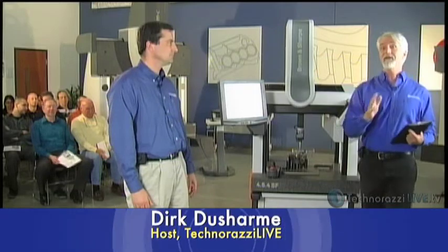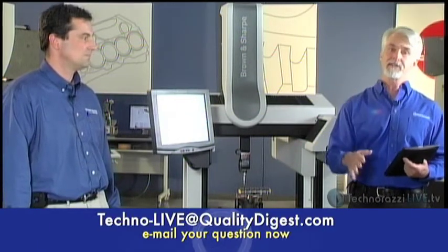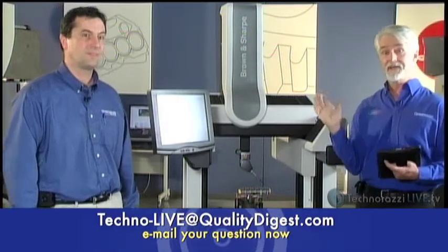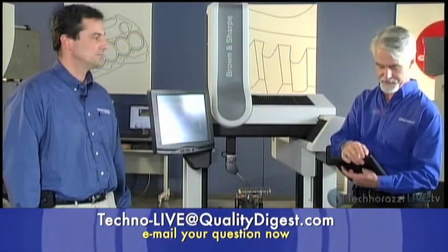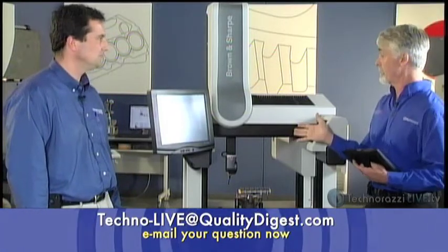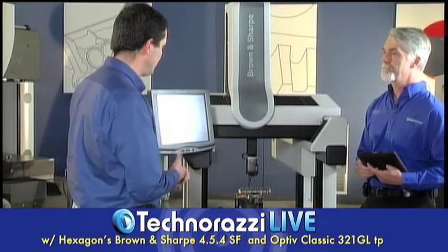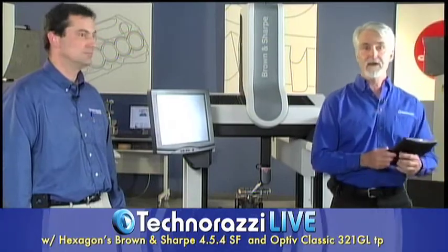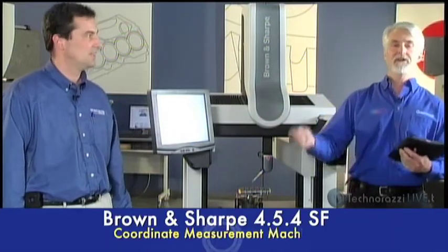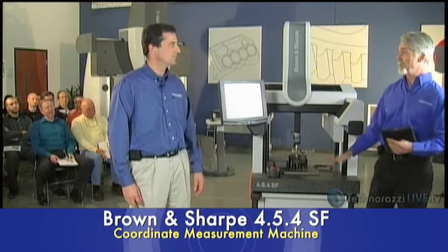Any questions, send them to techno-live at qualitydigest.com. We are going to move on to another product in a few minutes — continue to send questions even after we leave this product behind. Any kind of touch trigger probe right now and we're working on contact scanning probes. So this was the Brown and Sharpe SF shop floor CMM — shop hardened, rolls through any door, runs on 120 volts, no shop air. This is really a perfect entry-level machine for a smaller size CMM.